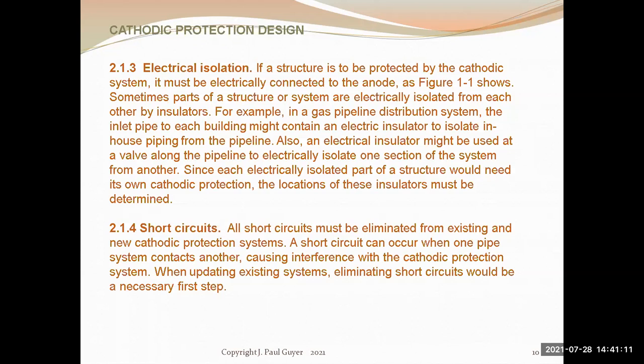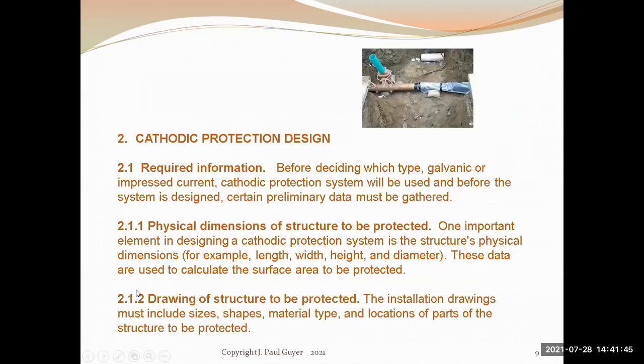Also, you need to be alert to avoidance of short circuits. So if something inadvertent in the ground, another pipe, is running around down there and happens to be touching your pipe that you're trying to protect, that results in a short circuit, which renders the cathodic protection system ineffective. So you have to have assurances that that is not going to be the case.